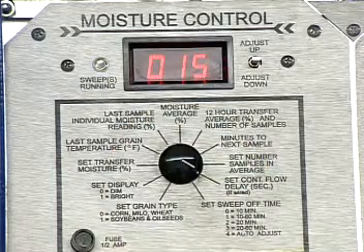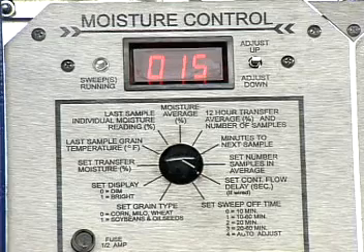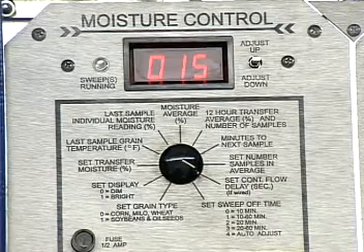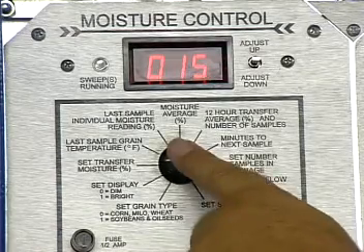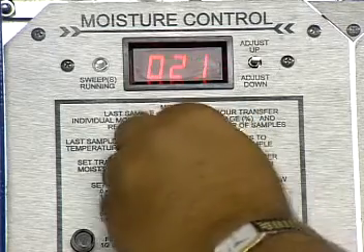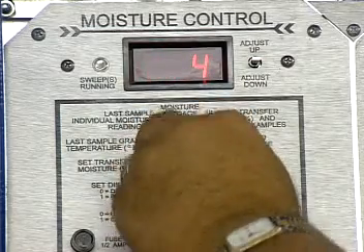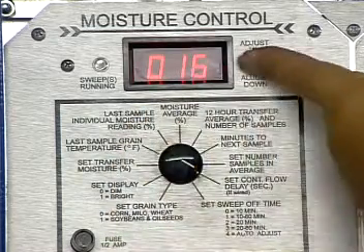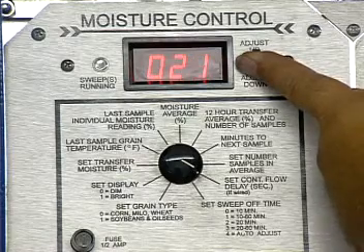Here's where you set the continuous flow auger in seconds, so it allows time to clean out. So when the dryer stops from up here, a too-wet sample comes over here and says I'm going to take 21 minutes to take another sample. It lets this auger clean out for 15 seconds. That's settable. You can go up to 20, 25 seconds, whatever you need to.